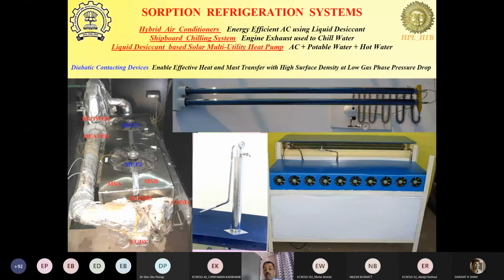Then this is a liquid desiccant based system where normally we want to maintain 27 degrees, 60% RH in the room, let's say. But the dew point temperature of that air is close to 14 degrees or so. Now to maintain a 14 degree dew point inside the room, we have to cool the air down below that, and then dehumidify that air.